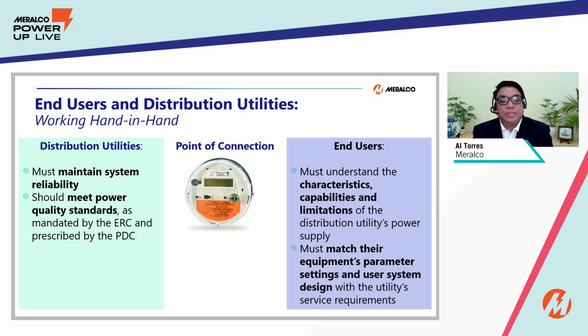End user and the distribution utility should work hand in hand. Now, the Meralco meter is the point of connection based on the Philippine Distribution Code. Basically, siya yung delineation natin, no? Meter upstream is the responsibility of the distribution utility, while meter downstream is considered the load side and is the responsibility of the end user. Next slide.